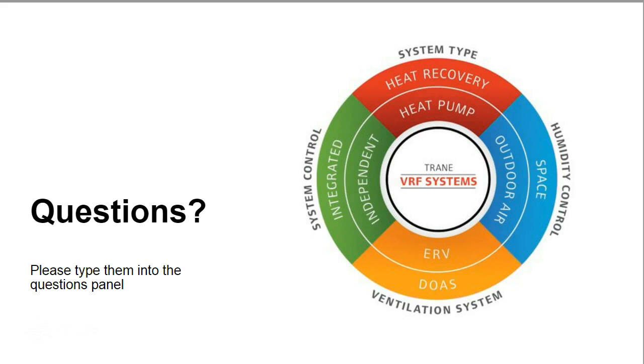All right, the next question is, what is the maximum cooling capacity size that VRF systems can handle? There are a number of ways to answer this question. Right now, some VRF manufacturers have condensing units well over 32, 34 tons. As for terminal zone units, I've seen the top end at 8 tons, although if more tonnage is needed, we do have the LEV kits, the linear expansion valve kits, which can be combined with a large air handler unit to use as a terminal zone unit. So basically you're creating your own VRF system with the air handler unit of your choice.